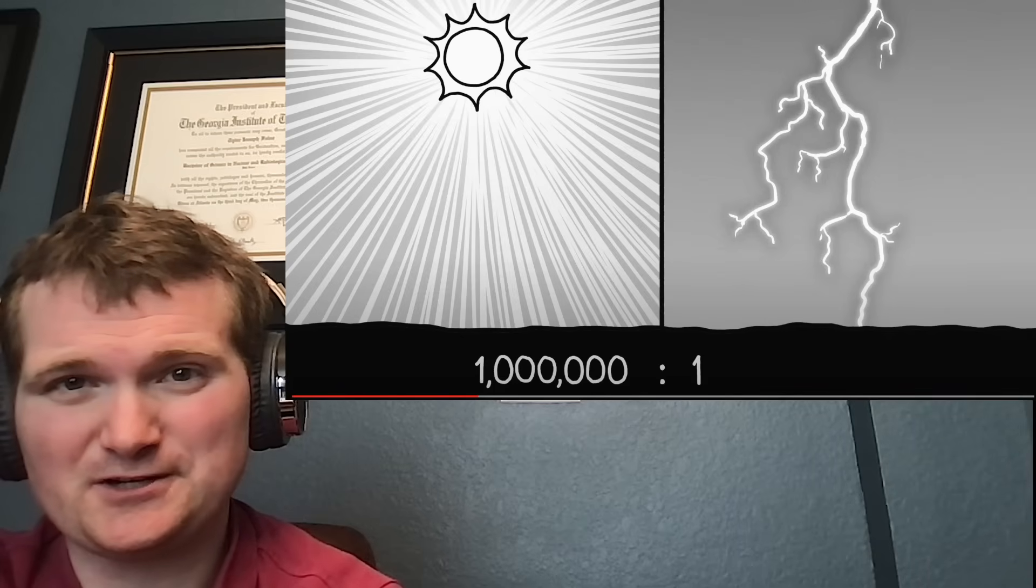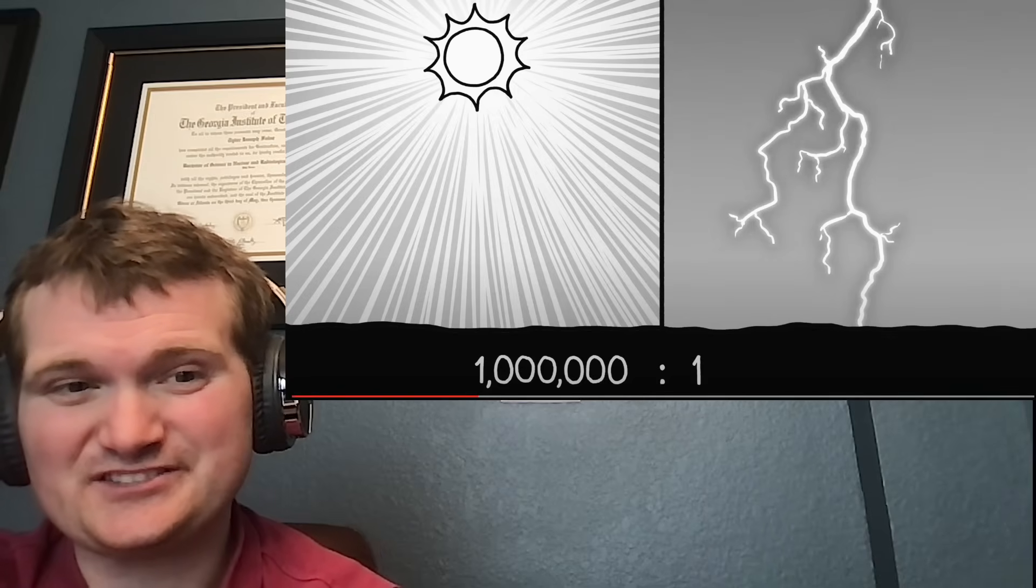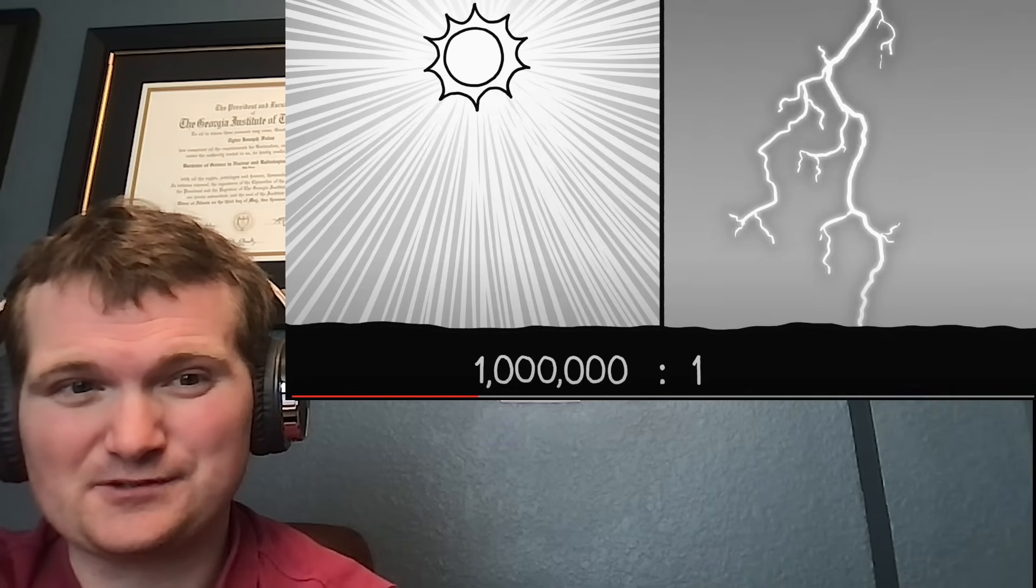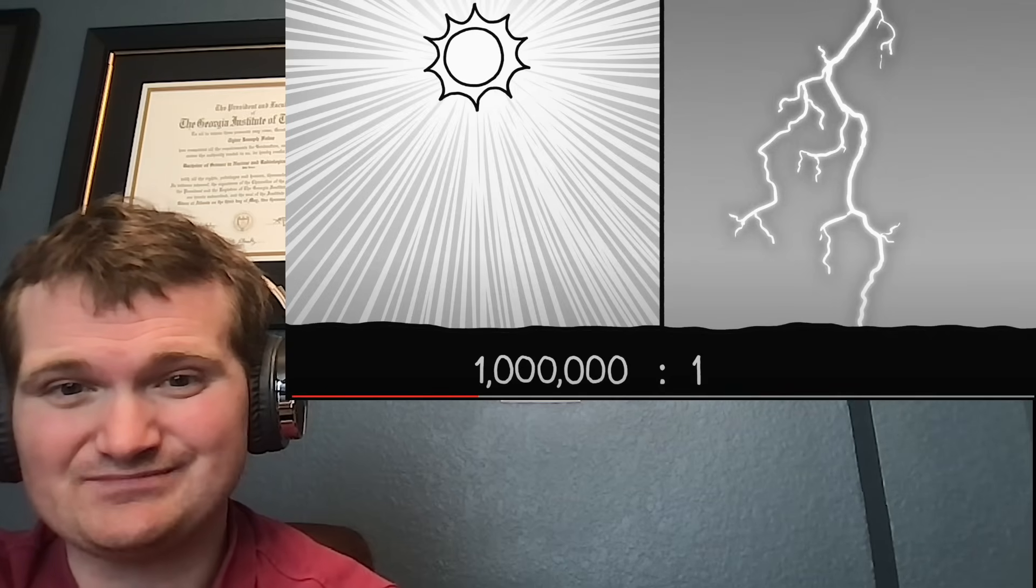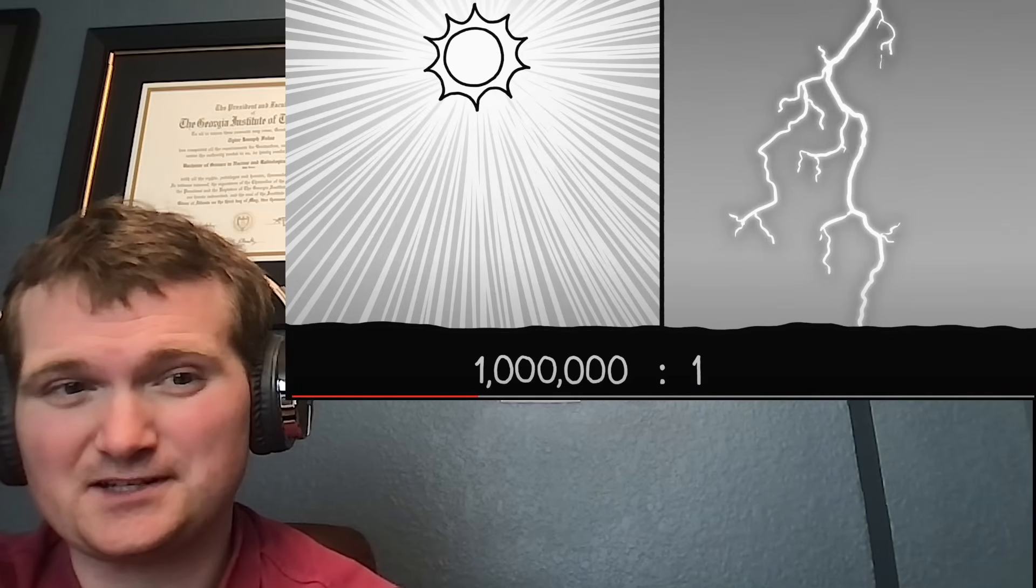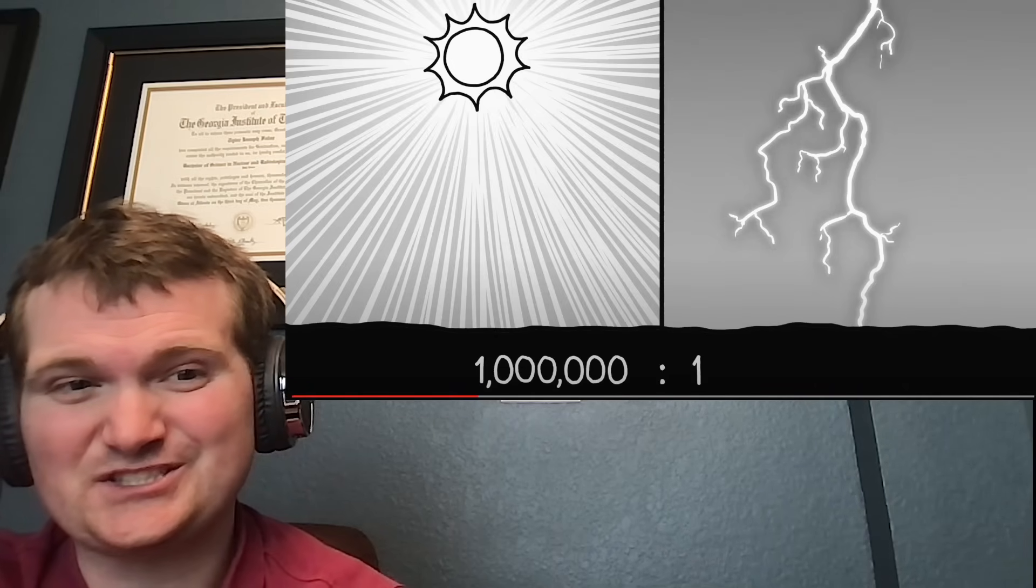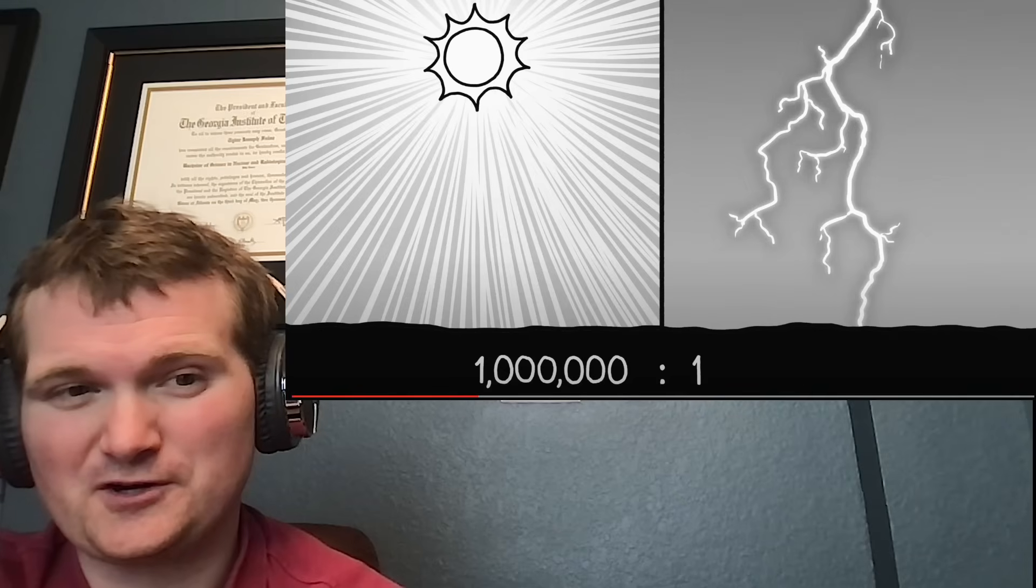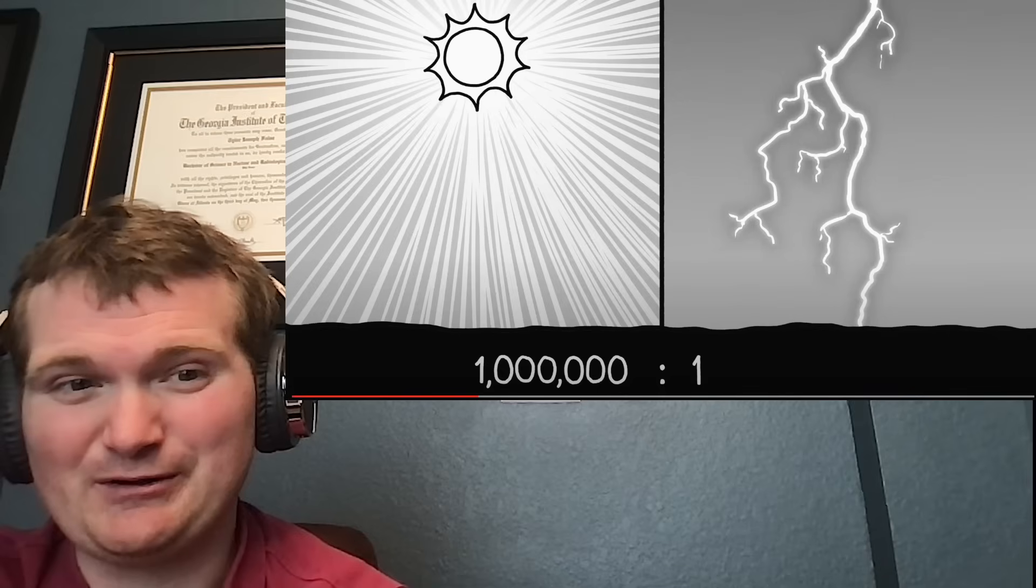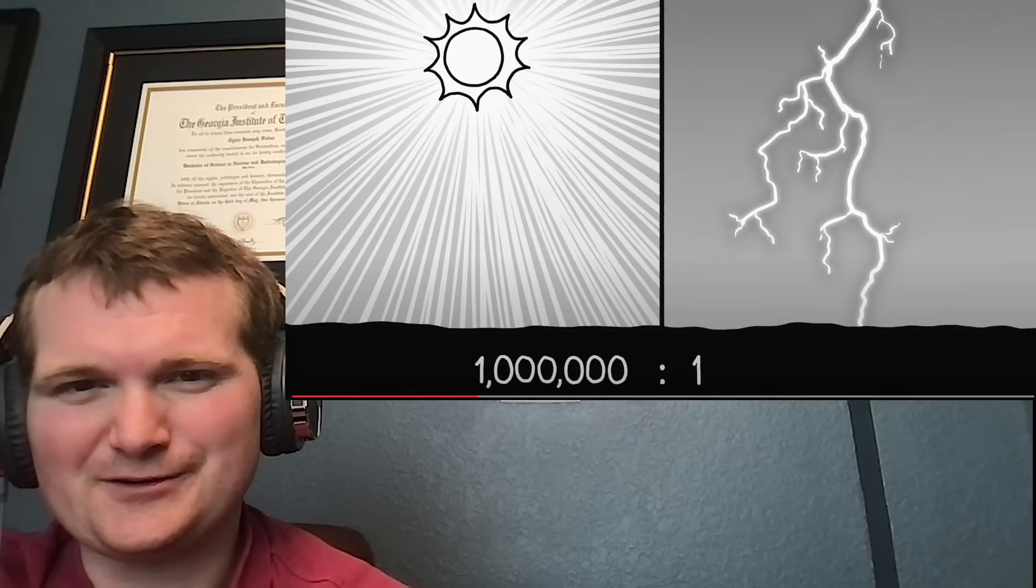And there are grounding grids installed around the plant, just conductive materials buried down in the ground to ensure it's dispersed safely into the earth. And just about every structure is grounded, not only from lightning, but just any sort of power surge. I mean, we're dealing with high voltage electricity. So surge arresters and suppressors protect against any kind of voltage spike, including the spikes of voltage you get from lightning. And there's protective relays in just about every electrical component for overcurrent, overvoltage, and undercurrent and undervoltage, for that matter, among just about every type of lockout device there is.